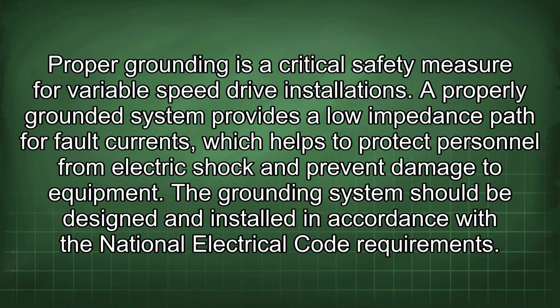Proper grounding is a critical safety measure for variable speed drive installations. A properly grounded system provides a low impedance path for fault currents, which helps to protect personnel from electric shock and prevent damage to equipment. The grounding system should be designed and installed in accordance with the National Electrical Code requirements.